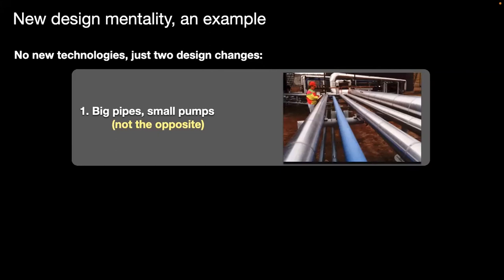A pumping system, pump, motor, inverters, electricals, all have to be big enough to overcome the friction. So their size and roughly their capex will fall as nearly the fifth power of pipe diameter. But the capital cost of the fatter pipe rises as only about the second power of diameter. So when we optimize the pipe as a component, we pessimize the system. Instead, optimizing the entire system at once yields fat pipes and tiny pumping equipment, so the total capex goes down.